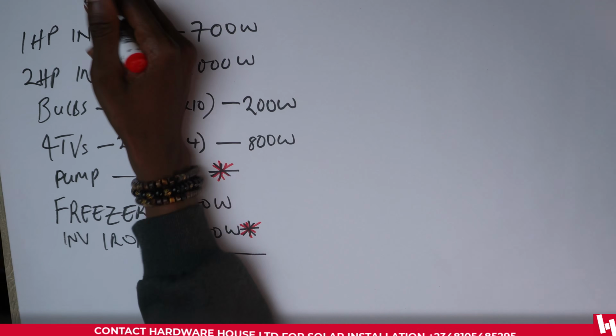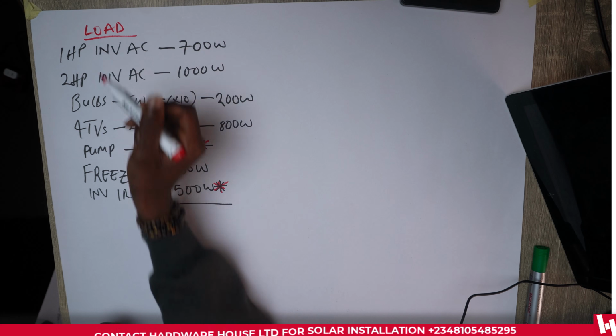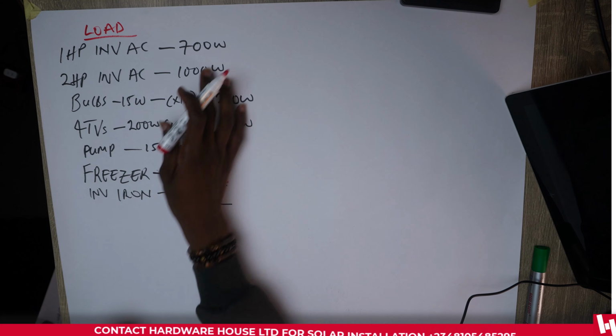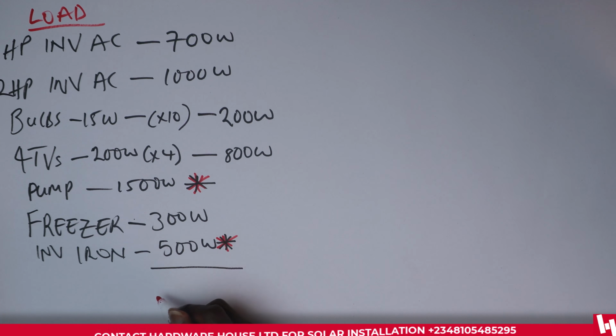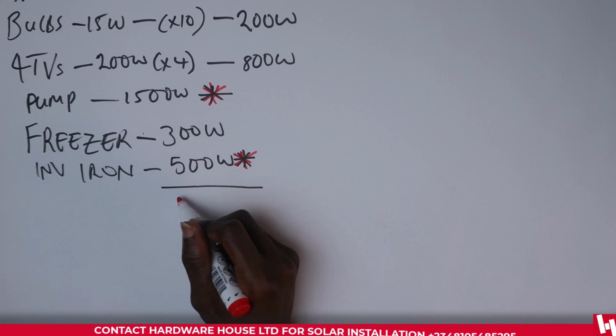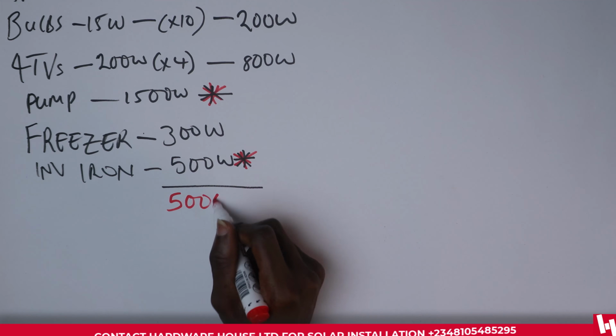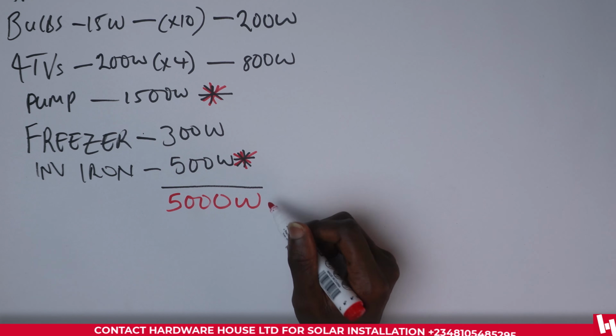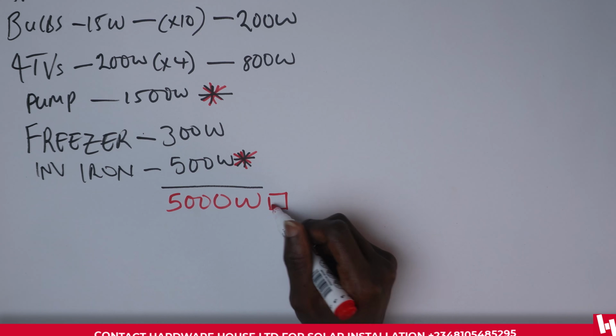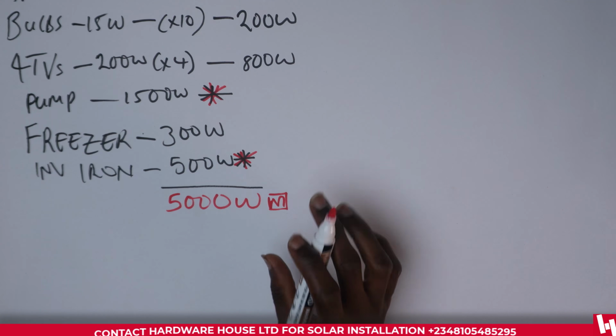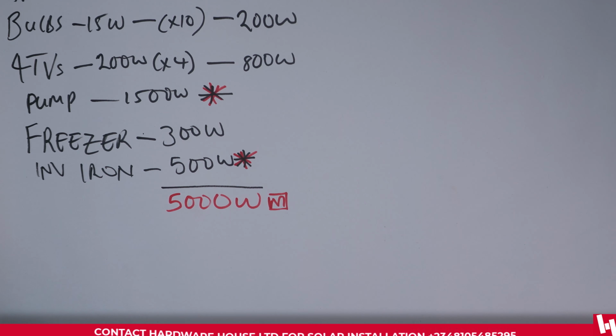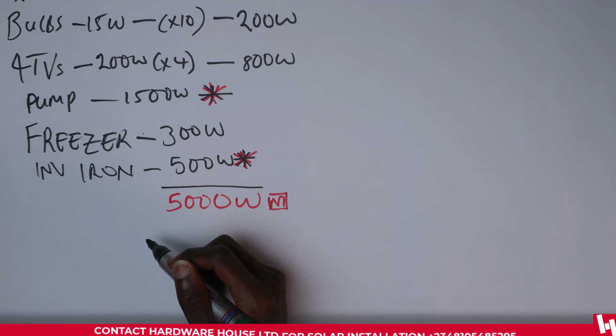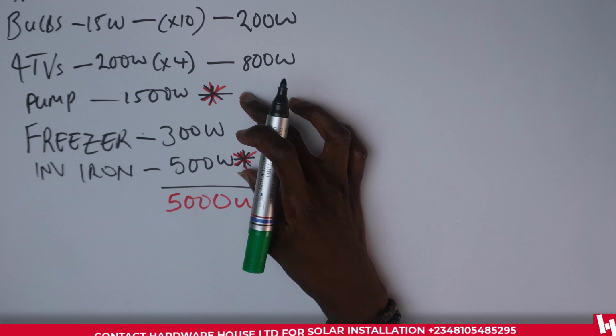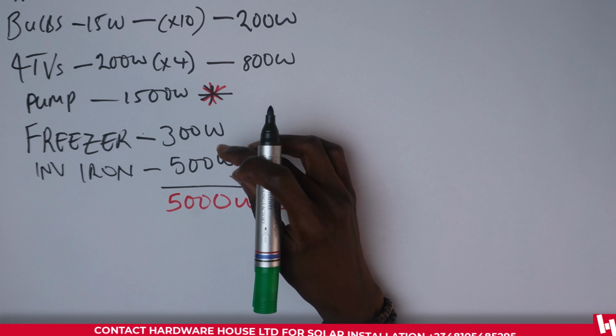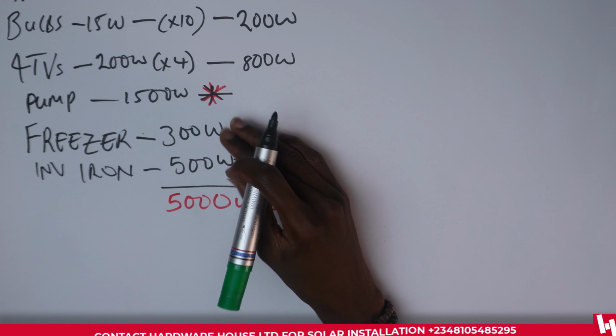So we'll add all this figure together to get a total power consumption of 5,000. So this is our maximum possible load, 5,000 watts. But then you don't have your pumping machine or your pressing iron running all the time. So we'd also have a nominal load, for which we would subtract 2,000 watts, which is a combination of the pressing iron and the water pump.